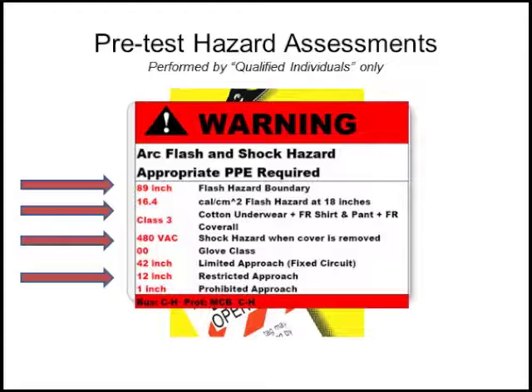00 gloves are good up to 500 volts. And we have our shock protection boundaries. A limited approach boundary of 42 inches, a restricted approach boundary for non-contact type work at 12 inches, and the prohibitive zone is 1 inch.